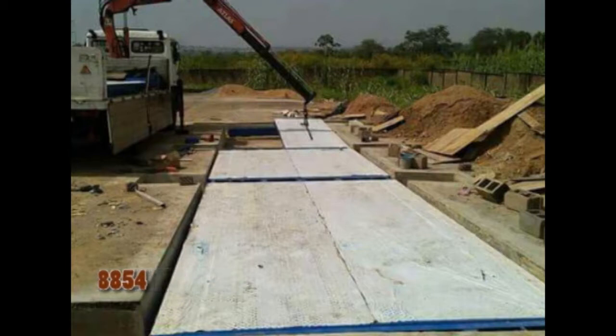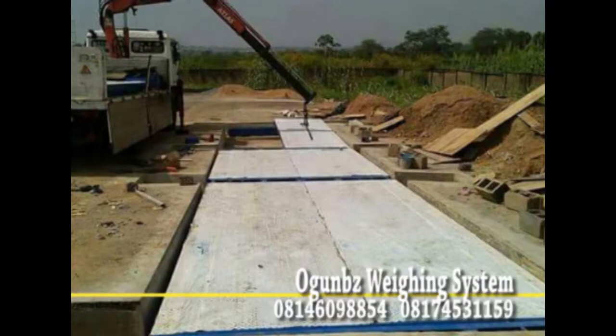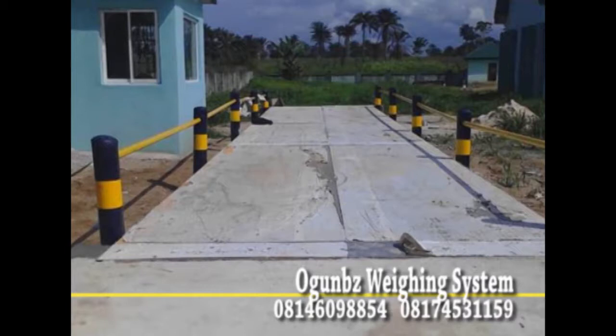Some very minor thing such as a rodent could destroy some very essential components of this weighbridge, and that could lead to a lot of problems. So rodent-proof protection is key. So that's very important too. So considering the operating temperature range of various components is essentially one of the key things that you need to consider. Like for instance, something such as a thunderstorm could happen. So grounding connection is essential to secure yourself from this phenomenon. So it's very key and very important. So preventive measures are very essential when it comes to construction of a weighbridge.